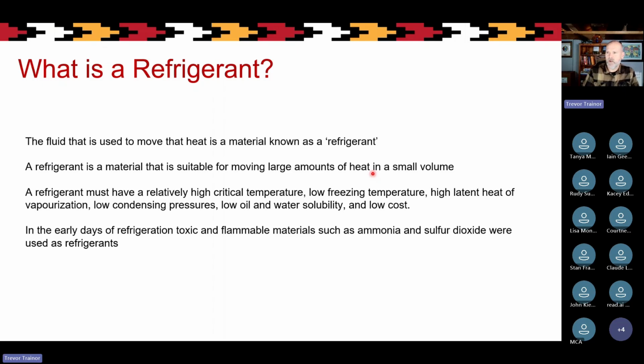It has to have a relatively high critical temperature, so it can become really hot without becoming volatile. It has to have a low freezing temperature. It has to have a high latent heat of vaporization, meaning it can hold a lot of heat before it evaporates. It has to have low condensing pressures, so we don't need a lot of pressure to make it condense. And it has to have low oil and water solubility so that it can function properly in the machine it's used in.